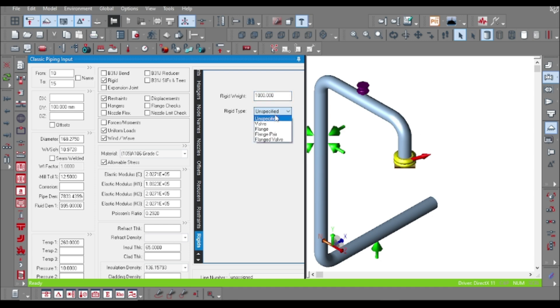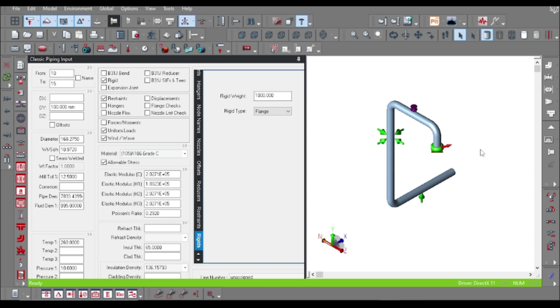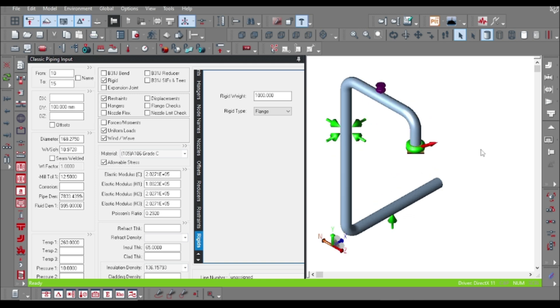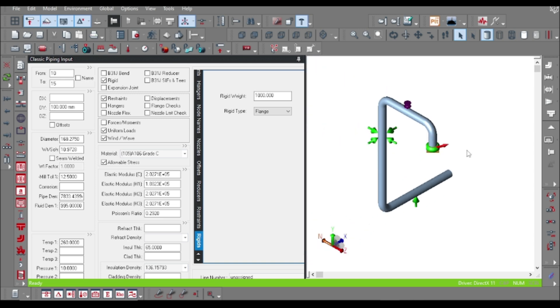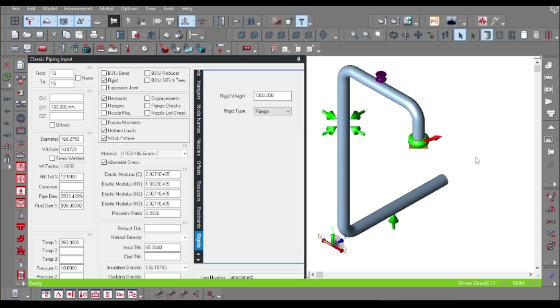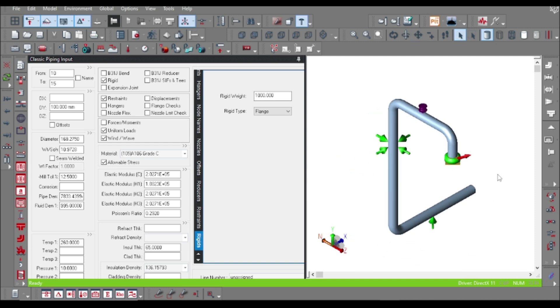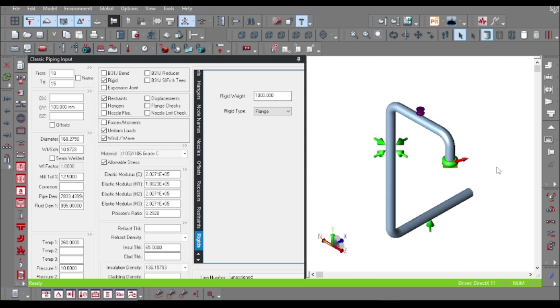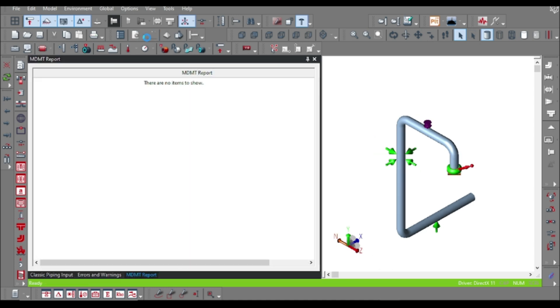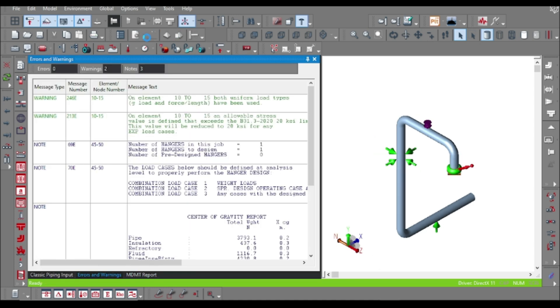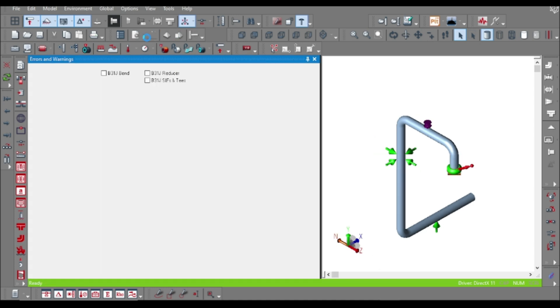As I told you, we have to run the model without snubber and note the operating displacement. Suppose I want to provide snubber at node 25, so let us run the model and note the displacement values for the operating cases at node 25.